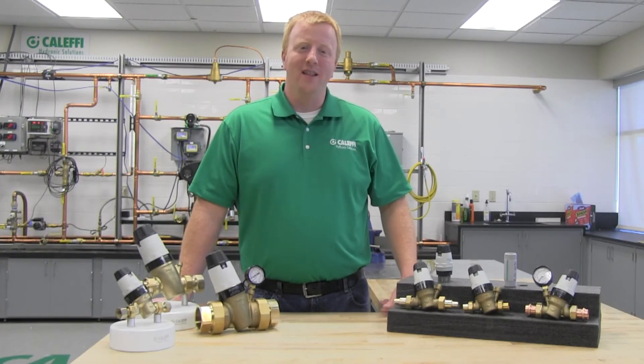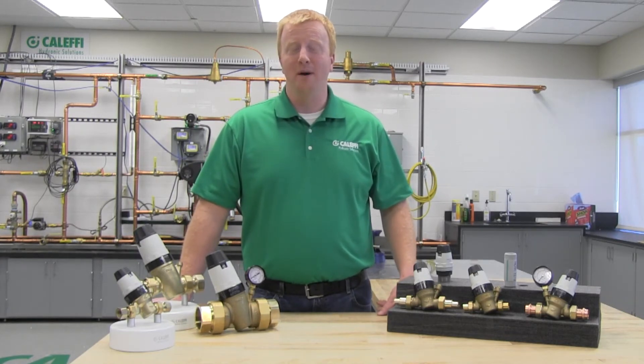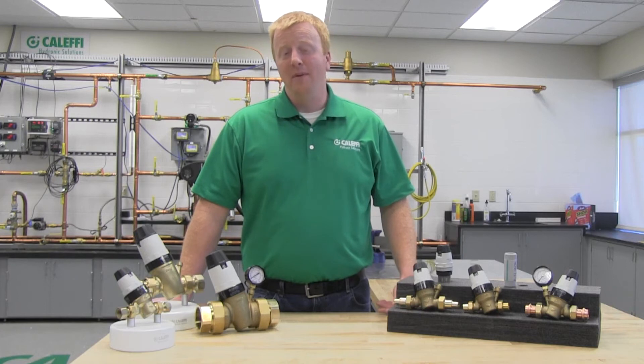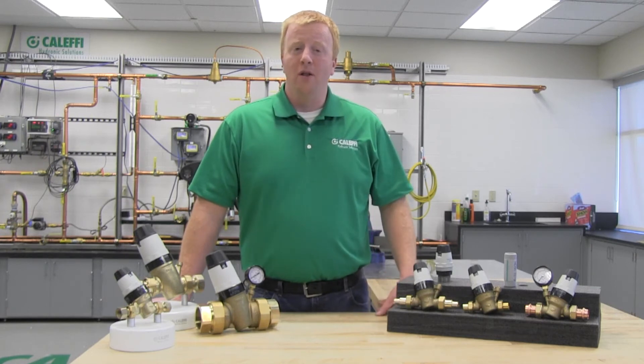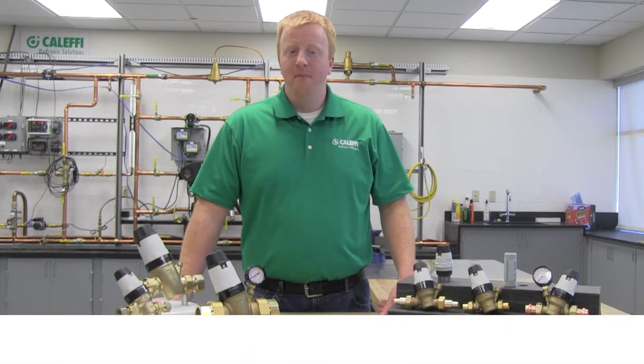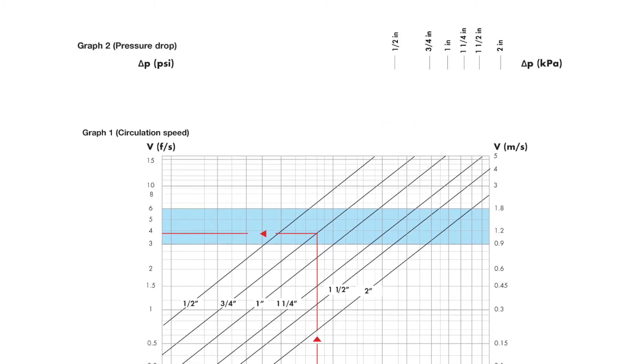So how do you size a PRV? We at Caleffi try to make this very easy. The first step is to select the valve size based on the target pipe velocity — typically you are going to be looking between 3 to 6 feet per second. Let's say for example you have added up all your fixtures and the total is 8 GPM. Using our chart, draw a vertical line up from 8 gallons per minute until you get to the target velocity, which is that blue band. In this example, the three-quarter inch valve is the obvious choice — at 8 GPM you will have a velocity of almost 4 feet per second.